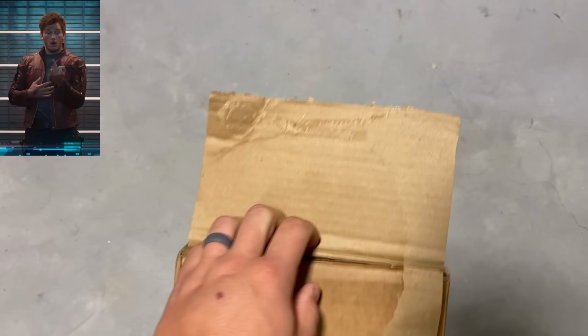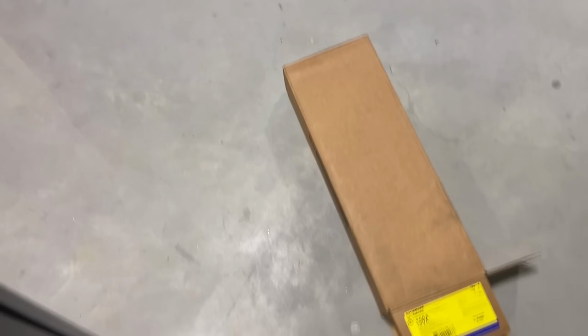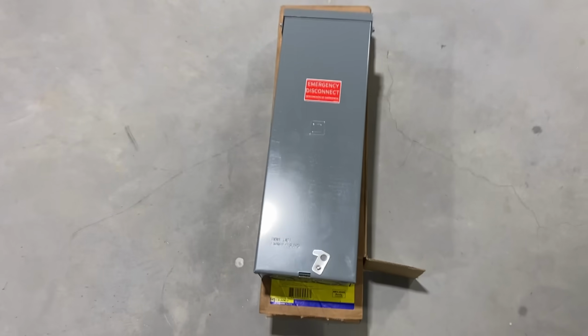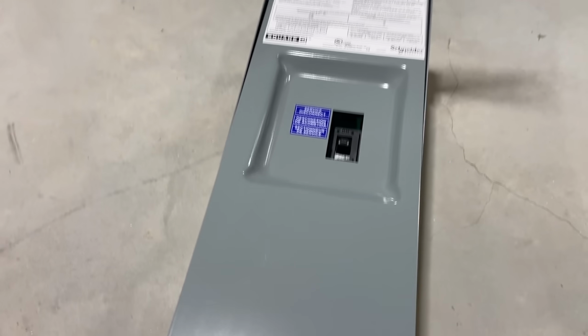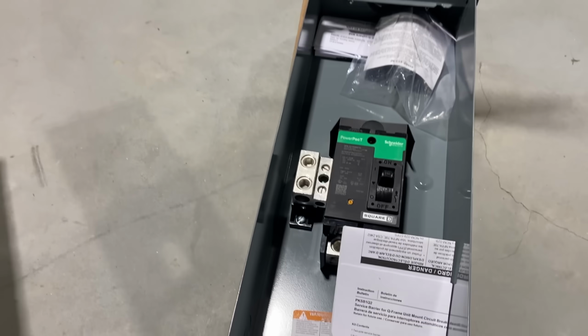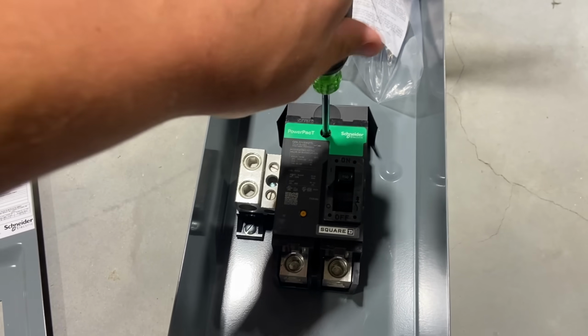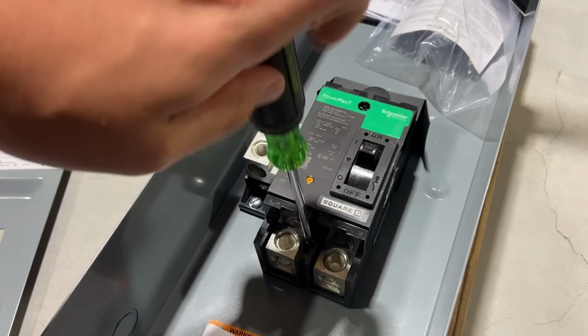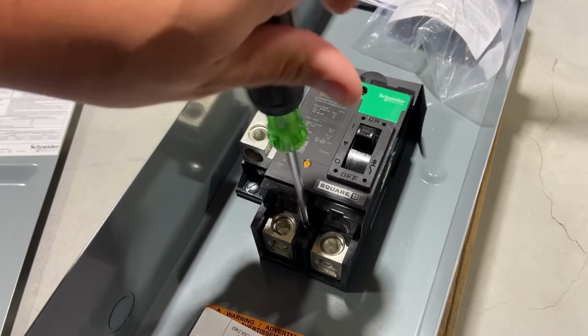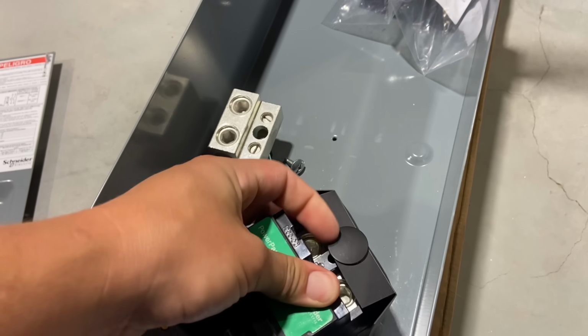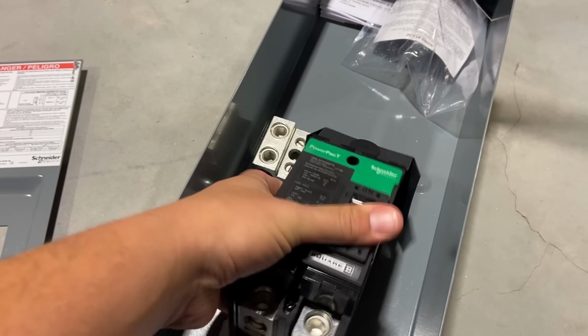I also needed a regular panel mount version of that 150 amp breaker, and the easiest way I could find to get one is to tear it out of one of these enclosures. You can get these enclosures pretty cheap, and sometimes it's actually easier to get this than it is the breaker itself. So that's what I did, I bought one just to steal the breaker out of it. So there's your pro tip for the day. That being said, I would never recommend that anyone violate the UL listing on an enclosure like this and steal parts out of it. That is absolutely a no-no.